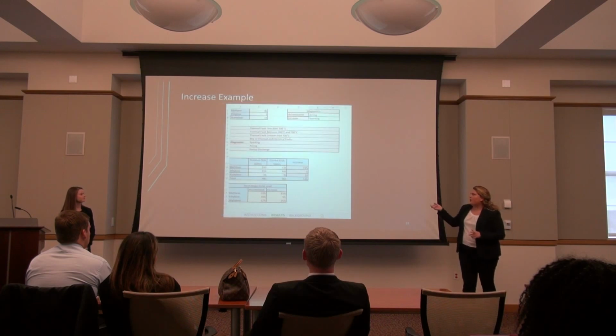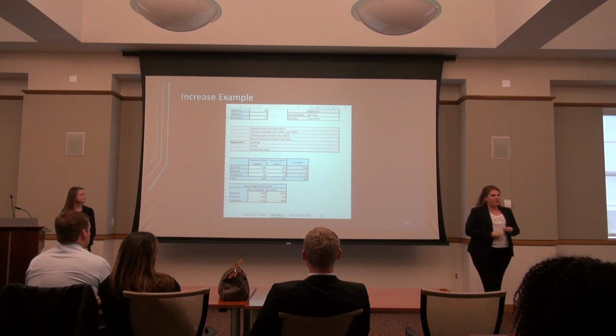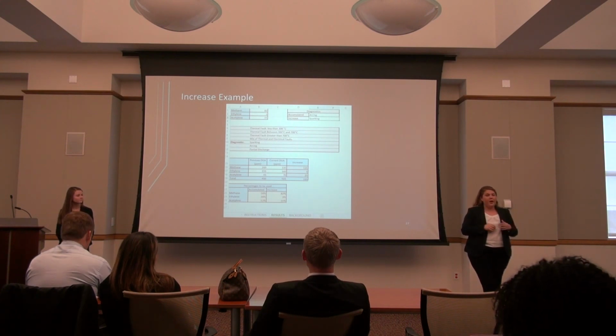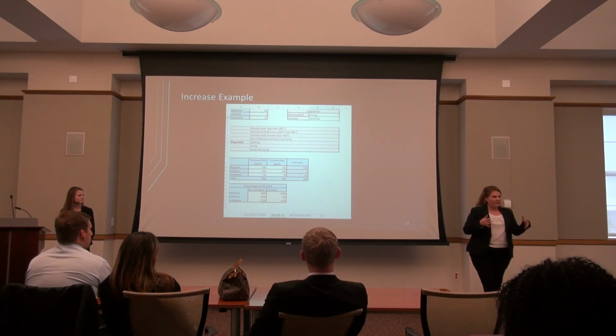On the next one, we use the increased values, put them at the top, and now we get sparking. So we know that they don't match up, it's not arcing for both of them. In a way that's kind of good, probably not necessarily a red flag, but because arcing and sparking are very similar in nature within the transformer, you probably should check it out and see if there are actually any other faults.